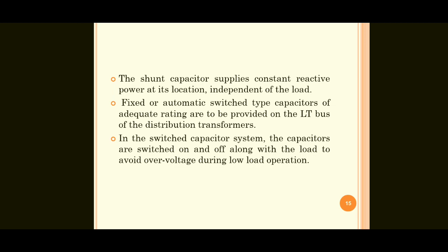Next point. In the switched capacitor system, the capacitors are switched on and off along with the load to avoid over voltage during low load operation. Generally at light loads, sometimes, not always, over voltages are present.